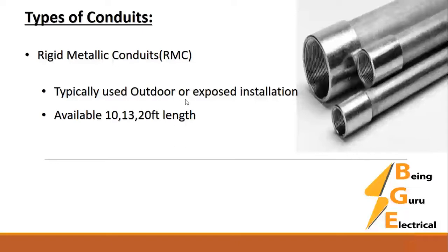The first type is Rigid Metallic Conduit, or RMC. It is typically used for exposed installations in residential, commercial, and industrial buildings — running on building fabric, inside false ceilings, or exposed on walls. It is available in 10ft, 13ft, and 20ft lengths. You can see the rigid metallic conduit in the pictures.